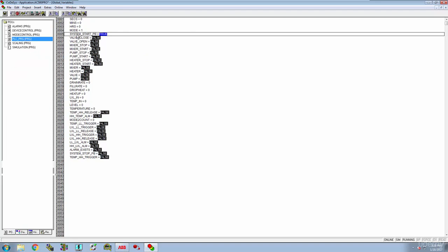I can check and see our mode. And our mode is now set to 1. So our system start PB works fine from here if I control it from here. It's just not doing the trick whenever I set it from inside of our PLC program.